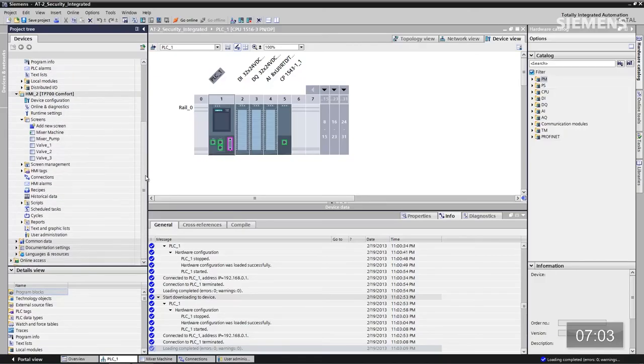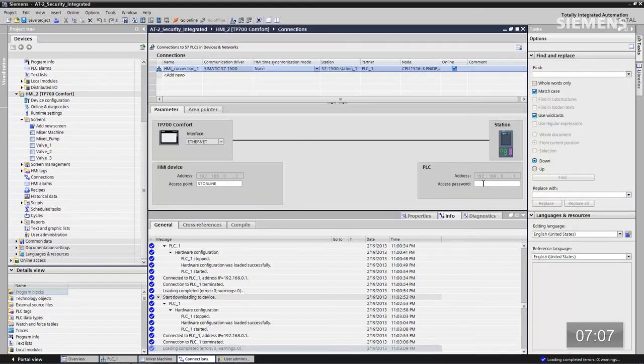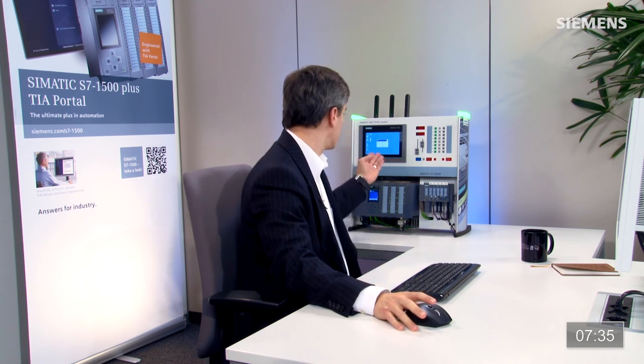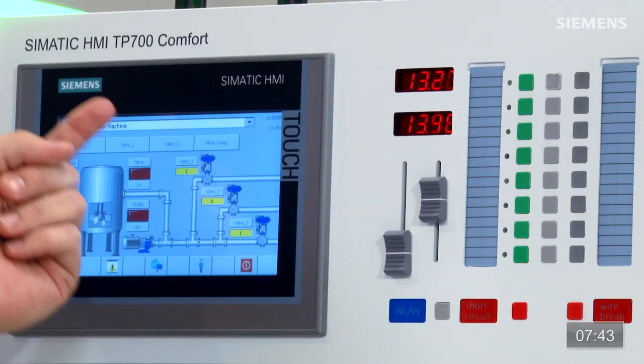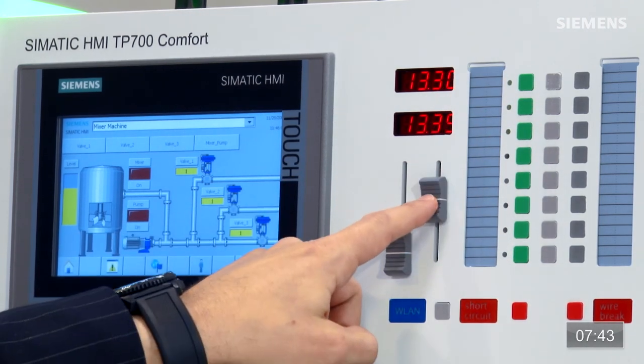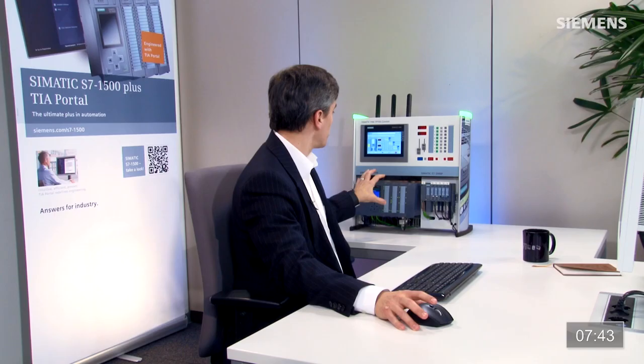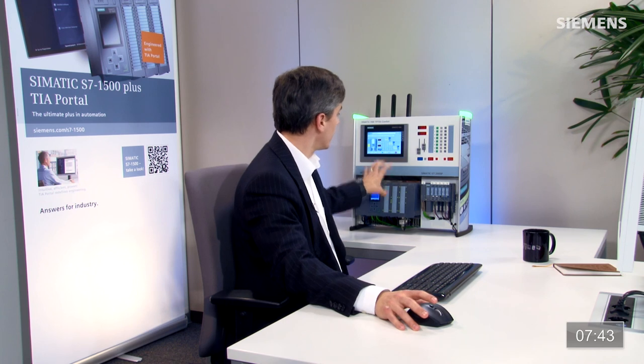Il ne peut ni lire ni écrire. Pour résoudre cela et fournir une connexion directe à ce contrôleur, je vais aux connexions. J'entre le mot de passe de la protection d'accès, c'est « Admin ». Je sélectionne le pupitre opérateur et je clique sur le bouton de téléchargement. Le système compile alors le fait qu'il y a une nouvelle protection de niveau 4 du contrôleur au pupitre opérateur. Je clique sur « Remplacer tout » puis sur « Charger ». Cela lance le chargement des écrans d'origine de l'administration des utilisateurs et de la nouvelle connexion sécurisée entre le contrôleur 1500 et le pupitre Comfort Panel, afin que seuls ces deux puissent communiquer l'un avec l'autre. Le transfert est presque terminé, l'écran se rafraîchit et on peut voir l'état des vannes et même les niveaux.